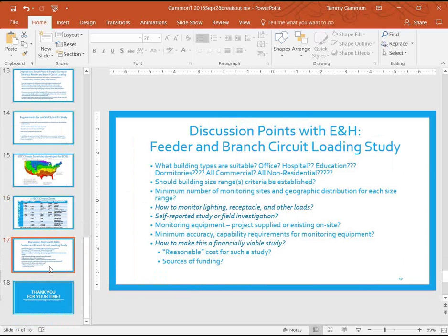I communicated with Brian Myers after our last meeting, and he pointed out that even in new construction, he rarely sees a dedicated lighting load. I can about confirm that I rarely see a load that is 100% lighting. In large office buildings with bulk 277 volt lighting, they're generally pure. Farther out in the life cycle, maybe some architect is pressing an electrical engineer to not put in something, so he'll do a 277/120, some kludgy things. But in general, for the larger buildings, the 277 volt holds, though there are exceptions. I hope that's a little bit helpful.